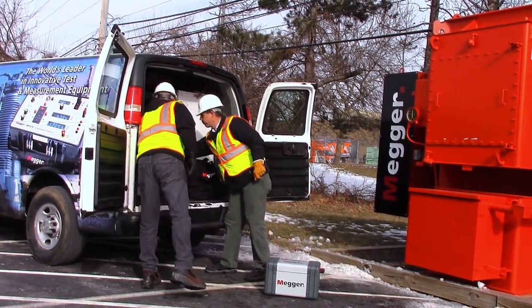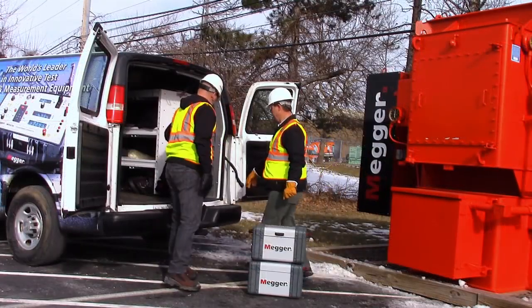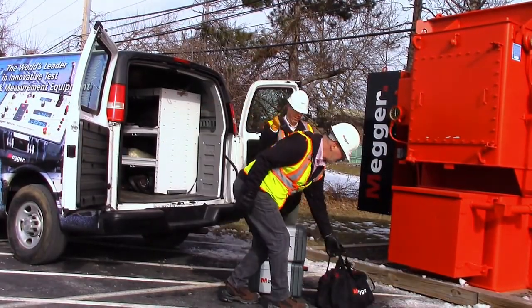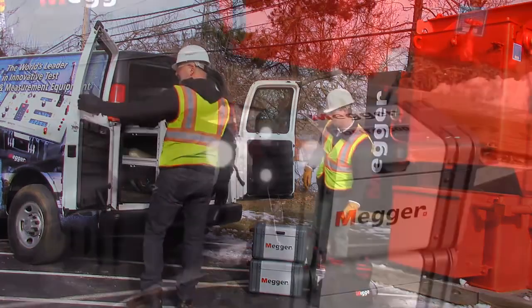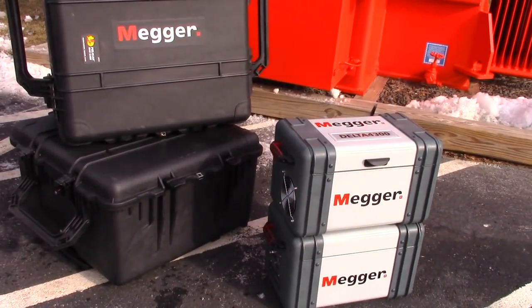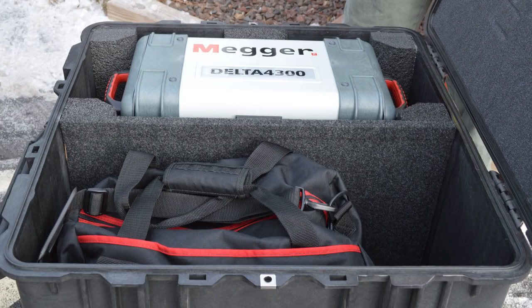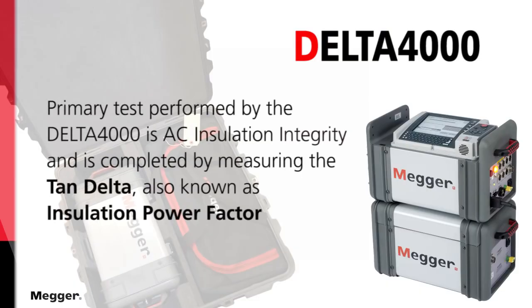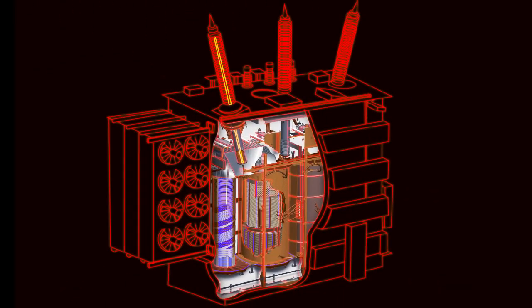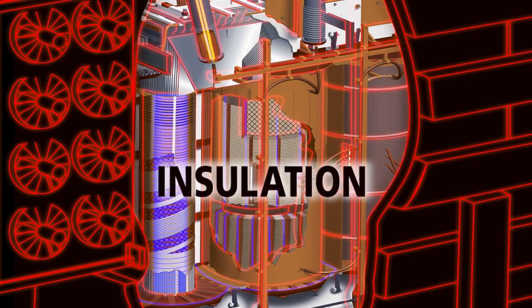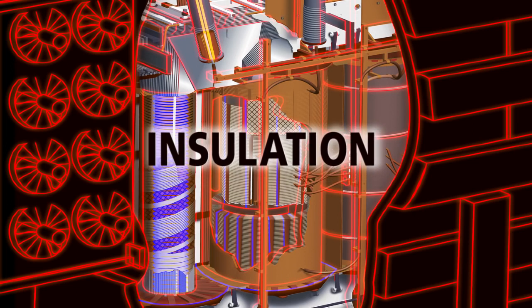It is important that testing conducted gives a clear indication that the transformer operates properly until next scheduled outage. The primary test performed by the Delta 4000 is AC insulation integrity, and is completed by measuring the tan delta, also known as insulation power factor. Transformers are divided into two major categories of construction and therefore into two types of testing, mechanical and insulation. Today's focus will be on transformer insulation, as we see this as the main determinant to the aging of transformers.